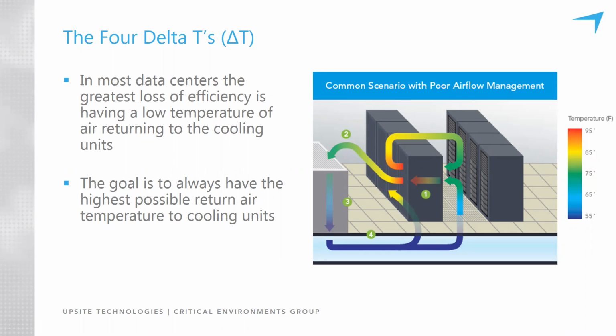So measuring these other two delta T's, 2 and 4, can provide a lot of insight into how much room there is to optimize your facility. The goal is to get those other two uncommon delta T's to around 5 degrees Fahrenheit. Moving from 30 degrees potentially down to 5 degrees is the goal. Below 5 degrees, you reach a point of diminishing returns. It's hard to achieve less than 5 degrees.